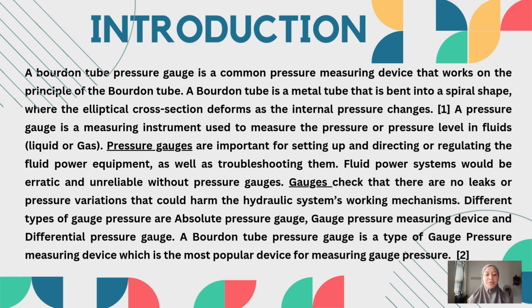Introduction for this experiment: a Bourdon tube pressure gauge is a common pressure measuring device that works on the principle of the Bourdon tube. A Bourdon tube is a metal tube that is bent into a spiral shape, where the elliptical cross-section deforms as the internal pressure changes.